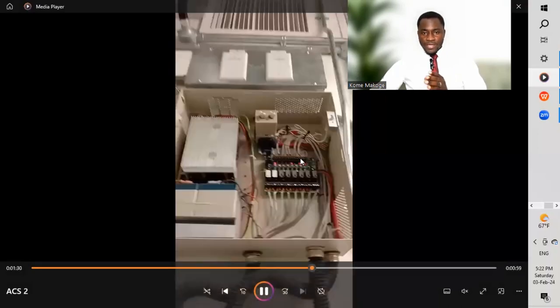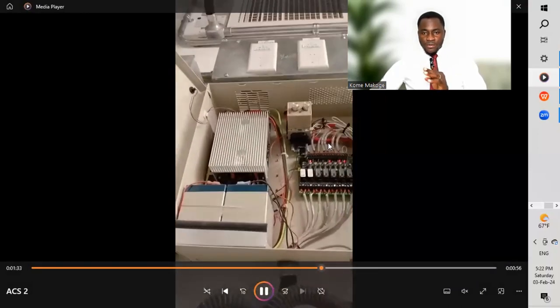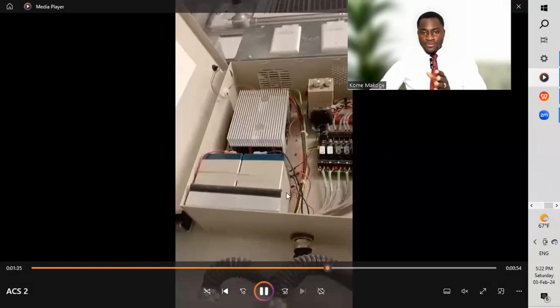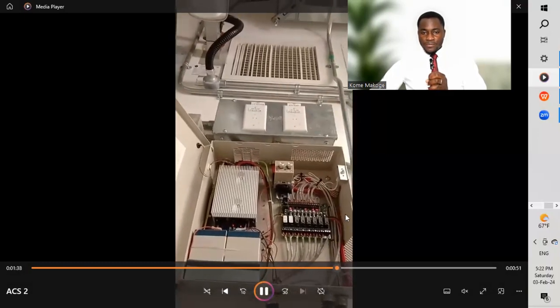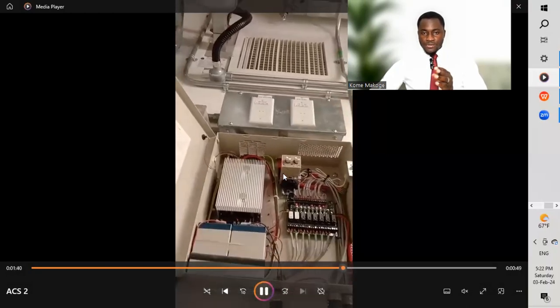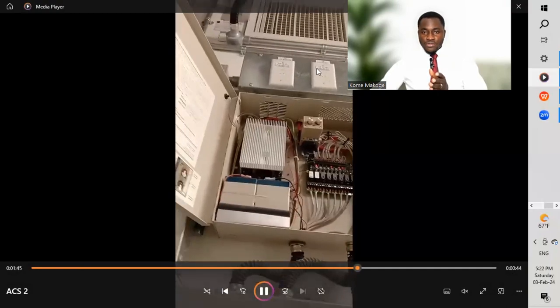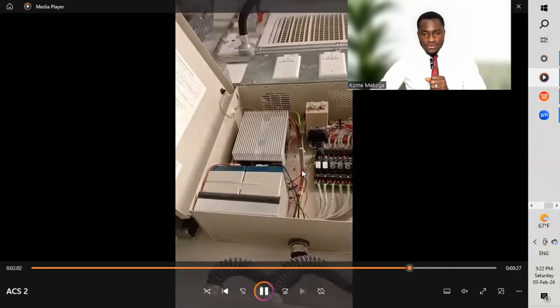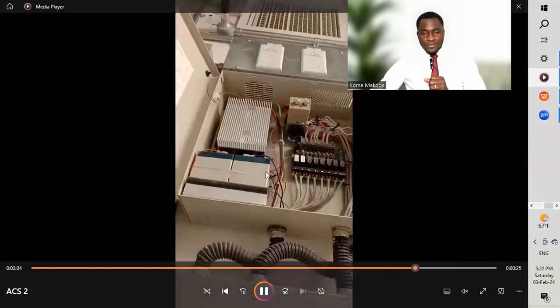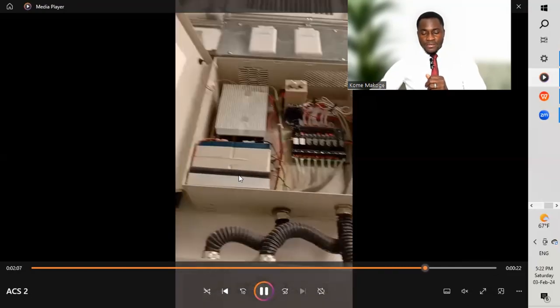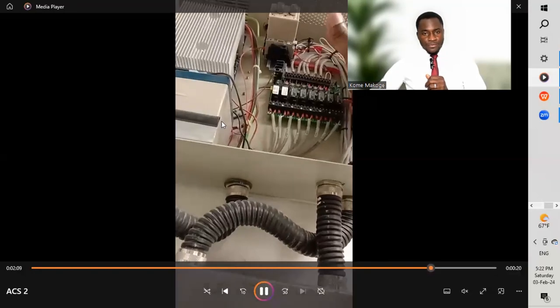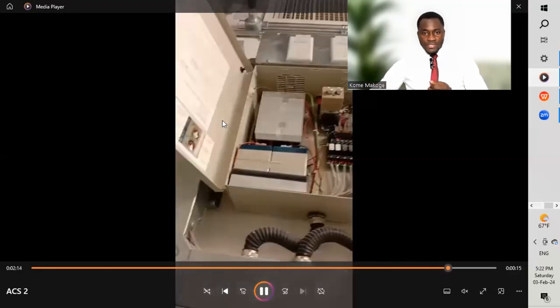Now we look at the access control panel itself. Opening it up, we can see how the cables have been installed. At the top are input devices, then output devices, and then a third-party cable coming from the fire alarm system. Two modules interface with the access control system. There is also a battery for backup for a period of time based on the project specification.